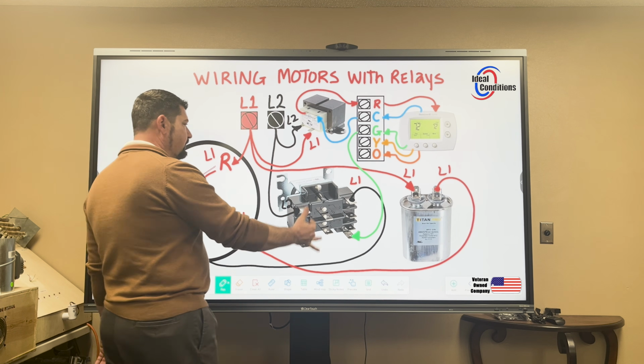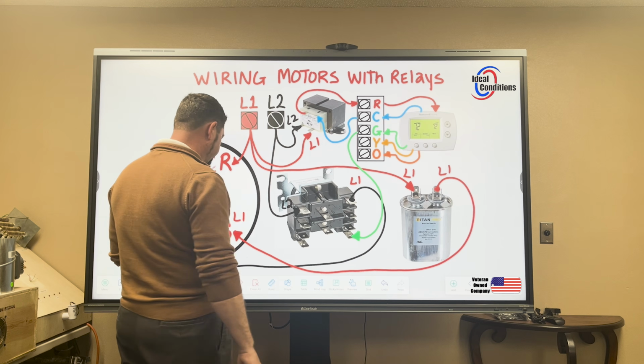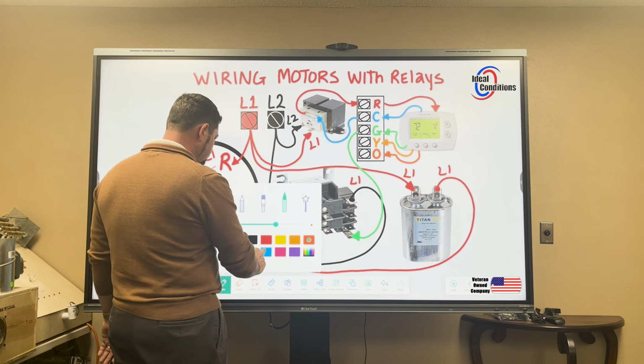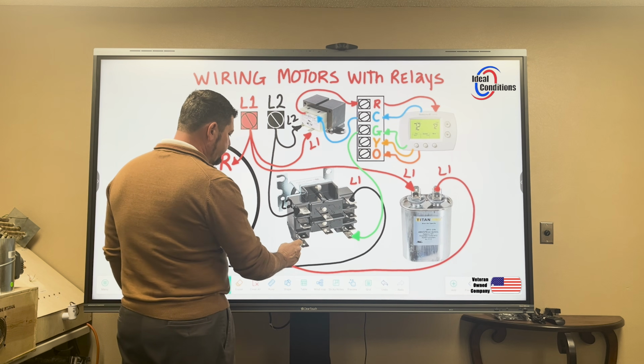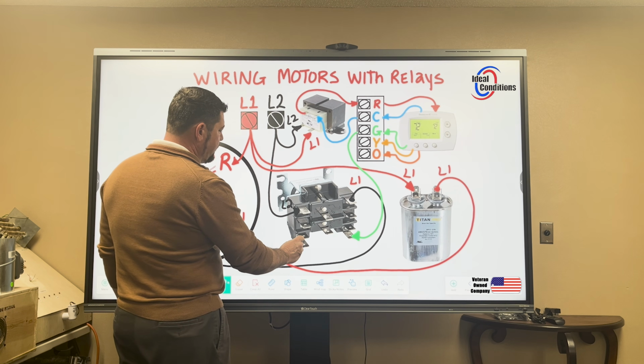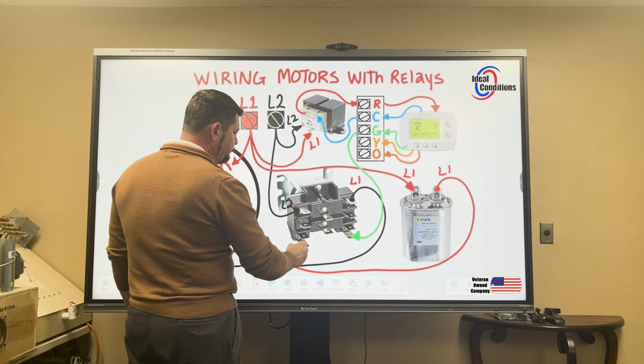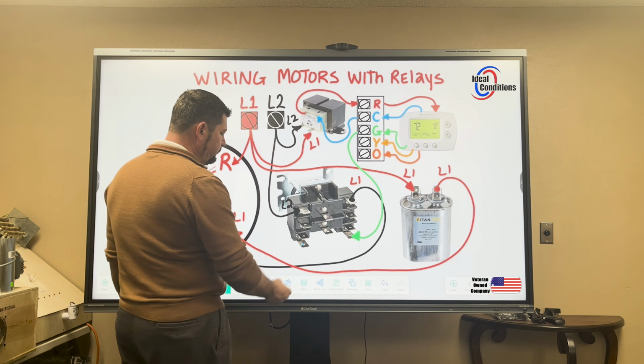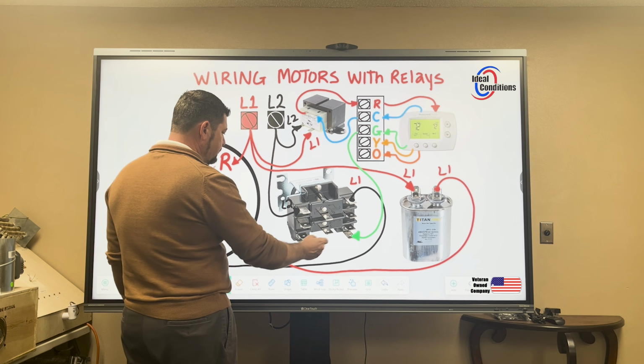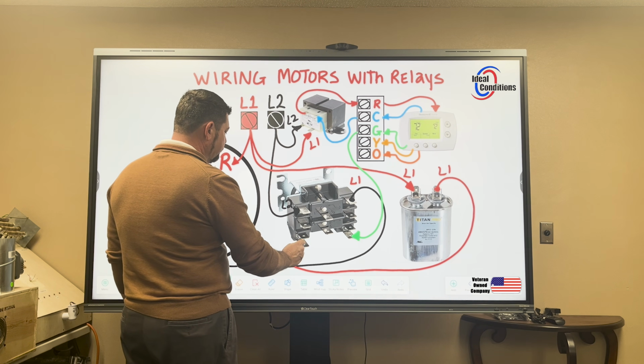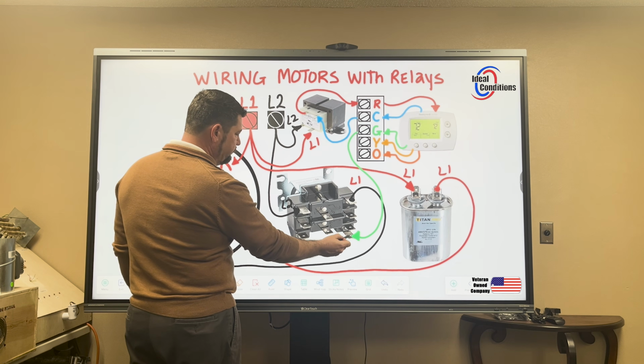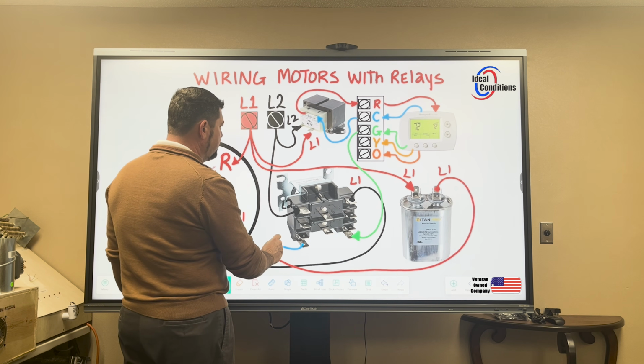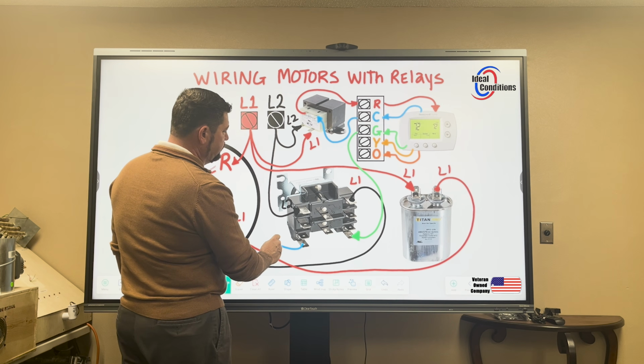Now this relay is still not going to energize until I have a common. So we're going to go ahead and give it a common. So I'm going to come out of this bottom side. It doesn't matter which one of these bottom terminals you put 24 volts on, as long as they're not on the same side. So we're going to come up and see how I want to do this.